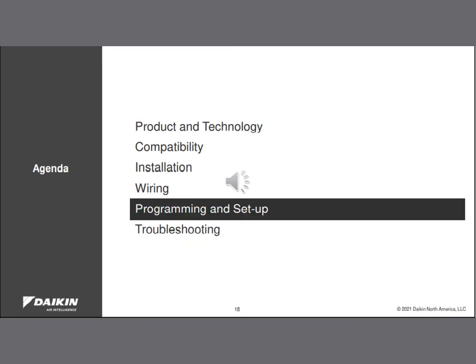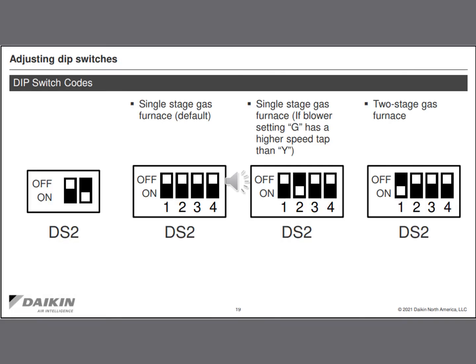Next, we'll talk a little bit about programming and setup. This is very easy with this adapter in place. There is a bank of dip switches that you will need to address when you're configuring the D24V Gateway. DS2 has 4 dip switches on it, and it comes defaulted to single stage gas furnace settings, which is all 4 dip switches in the off position.